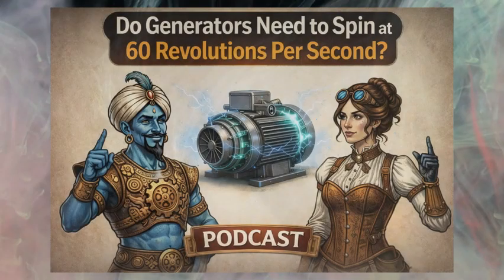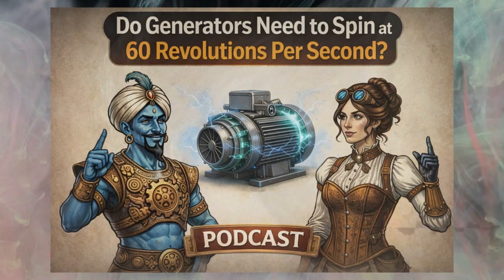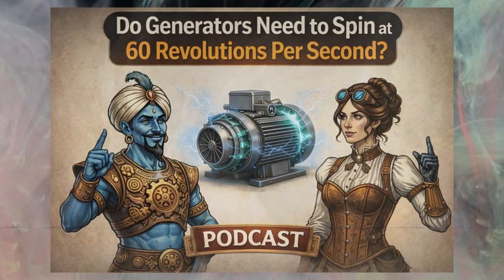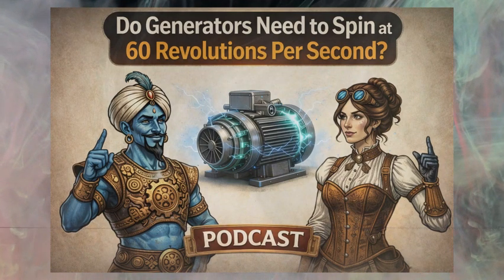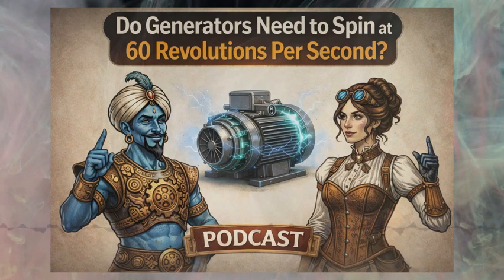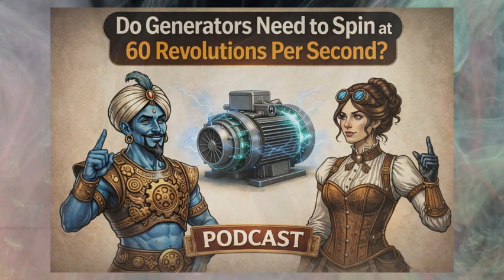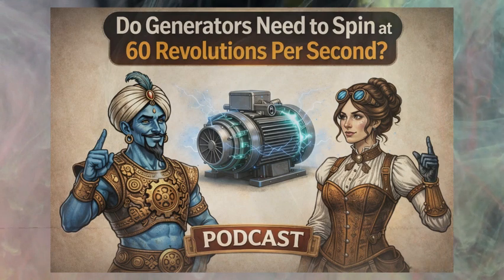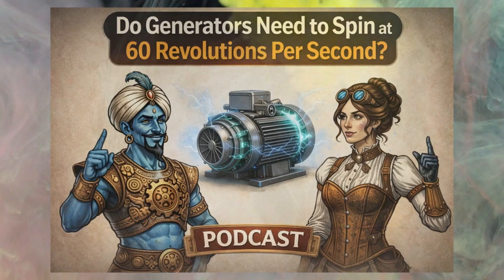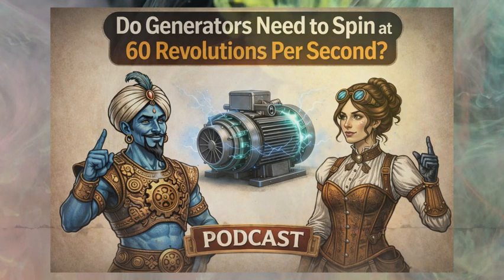Machines are rated. We think of power in watts, but alternators are rated in kVA, kilovolt amperes. Why is that? Well, the useful power a load consumes is in watts or kilowatts, but the alternator doesn't care about the load's efficiency. The alternator's physical limitation is heat, the heat generated in its own windings.